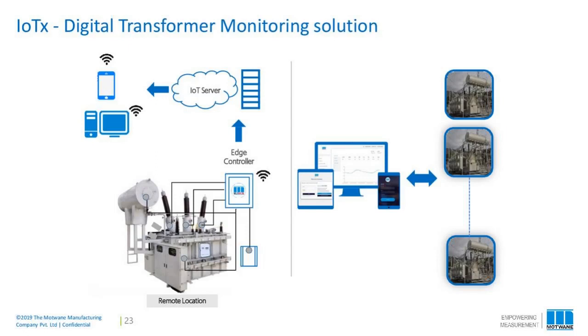Sure, I can take this one. So actually, this device itself can be integrated with your transformer pretty much out of the box, pretty directly, as long as it has the right set of inputs, which is a signal input to the IoTX device itself. So it can work with your existing OTI, existing WTI, existing oil level indicator or oil level sensor.